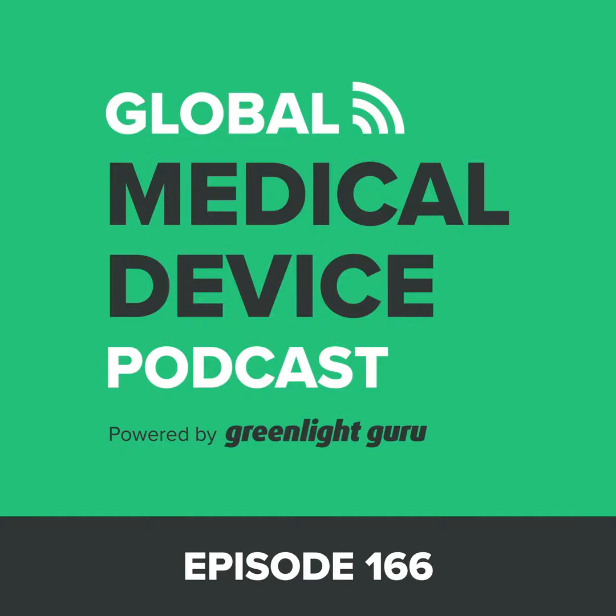I never take that as coming down from upon high, because in some cases, some of the testing that they recommend, in my opinion, as a professional biomedical engineer, is not necessary. And in other cases, what they're recommending might not be enough, and we need to do more. Yeah. So I believe those so-called standards, and I'm putting the word standards in air quotes again, are just a starting point. It's not gospel.